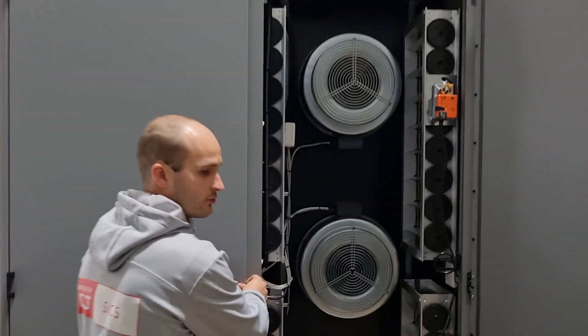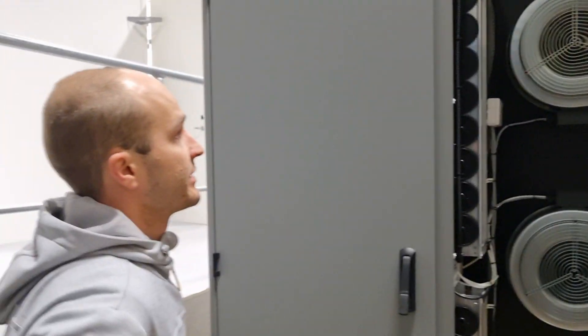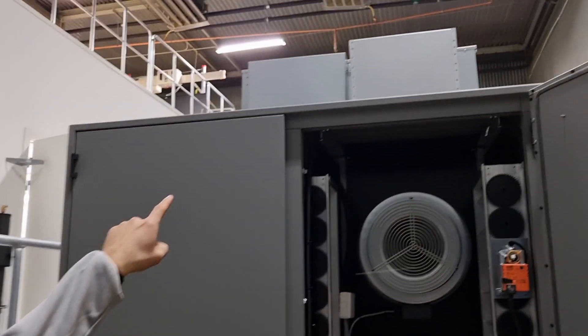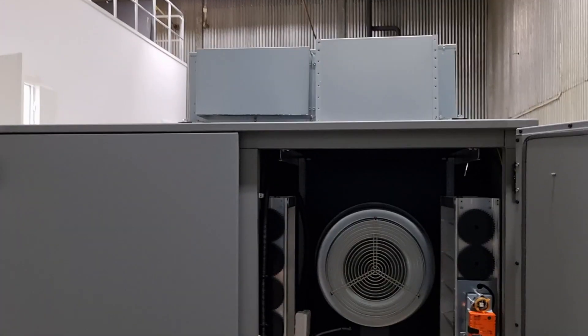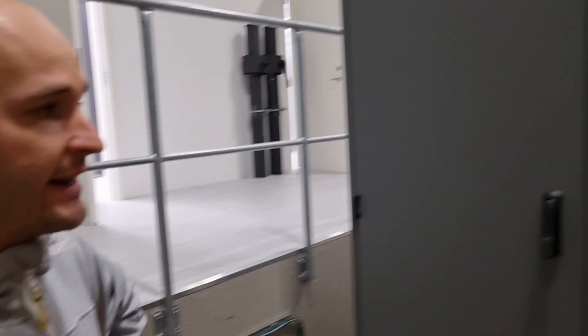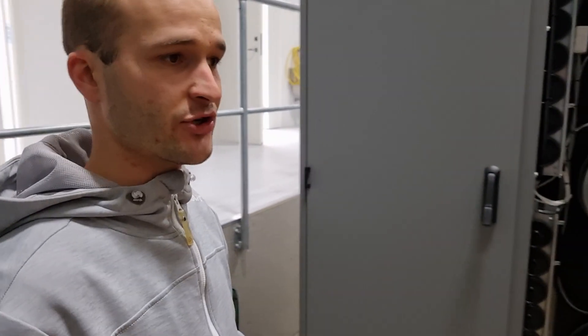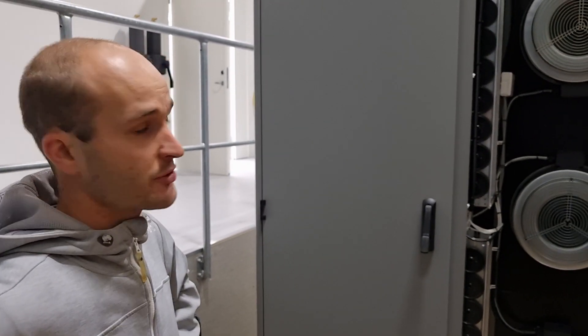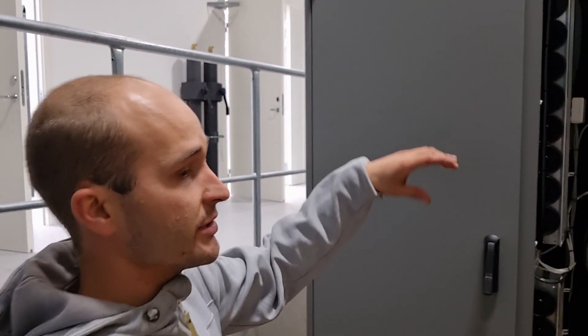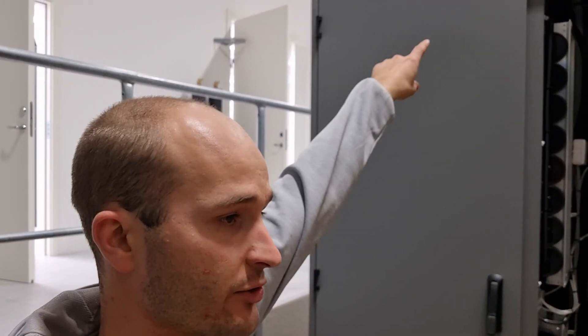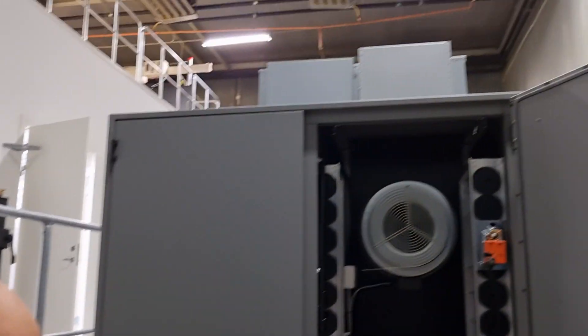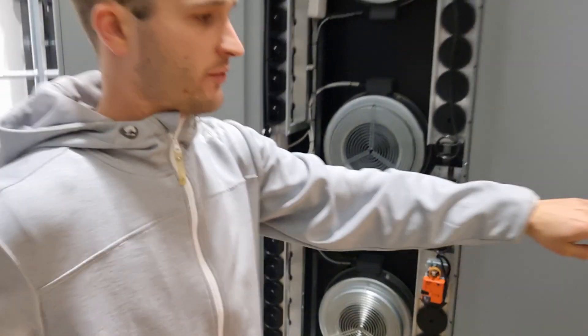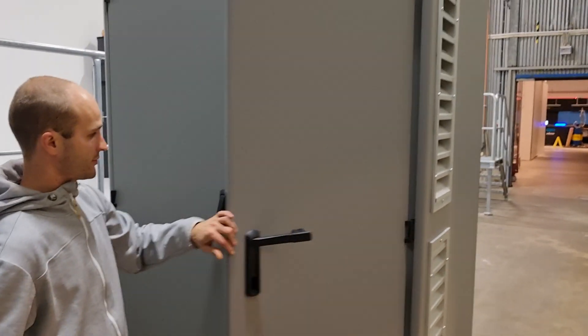Another unique aspect of the cooling system here is that we have a heat pump, a DX refrigeration unit mounted on the top. So if it's a warm summer day and the outside temperature goes above 23 or 27 degrees, which is the maximum temperature allowed for servers, we can actually pass air through the cooling unit and actively cool the air down to achieve the recommended inlet temperature to the servers.